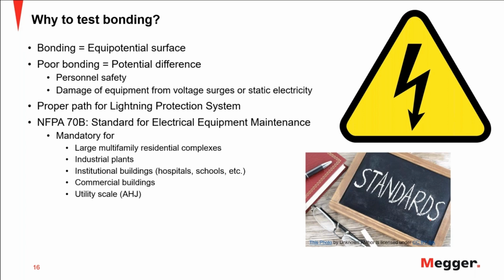And if we want to give another reason why to test bonding, you could easily say it's because the NFPA standard 70B tells you that you have to do that, and it's mandatory for large multifamily residential complexes, industrial plants, institutional buildings, commercial buildings, and also utility scale installations. And of course, this depends on the authority having jurisdiction, but that's one of the main things they check. It's basically safety of personnel.